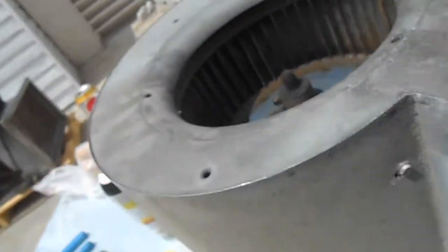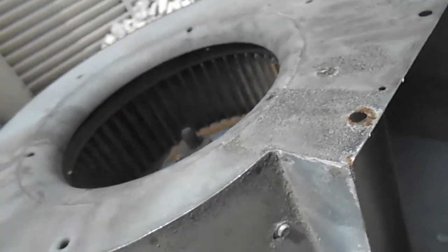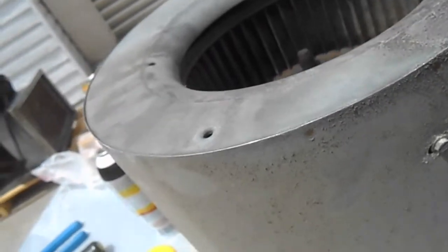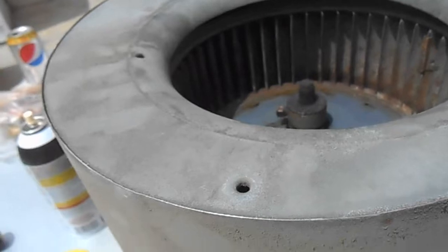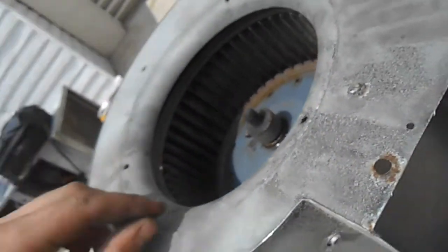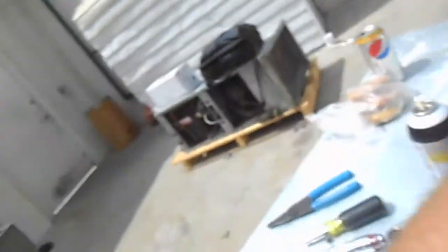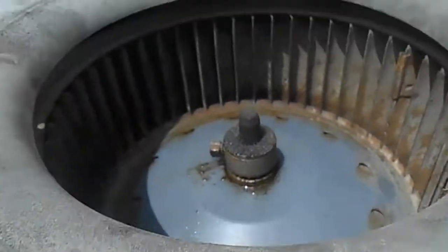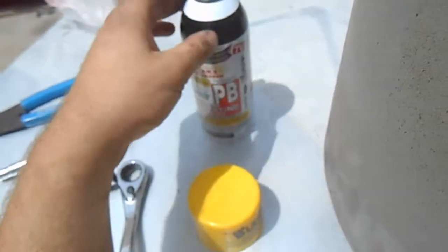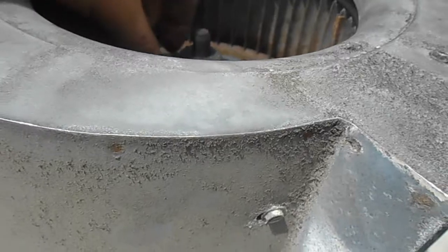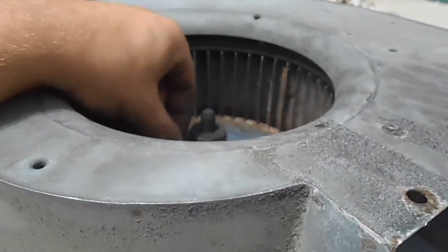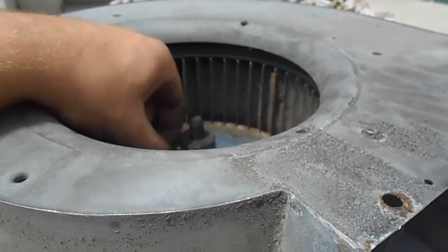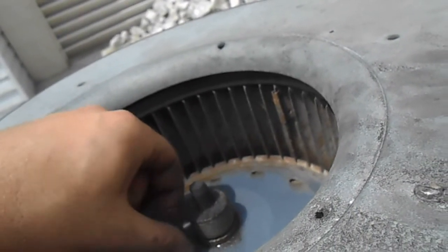We're out here in the equipment yard with this blower housing and motor and wheel. What we're going to do is put the puller to it and take the old motor out. So, the first thing you've got to do, I sprayed it with penetrating oil already. I used PB Blaster. Anything will work though. Then, you've got to take this little lock nut or bolt loose. You don't need to take it all the way out. Just make sure it's loose enough to get the puller on there.